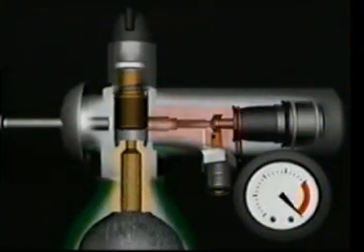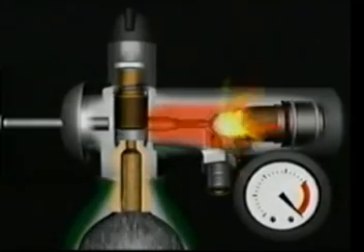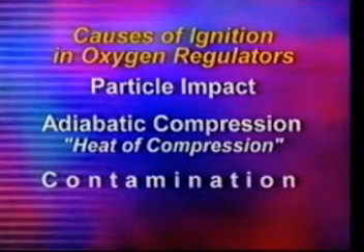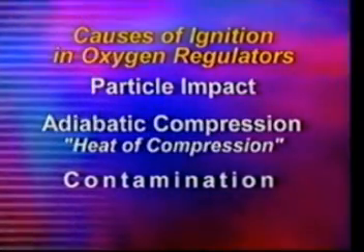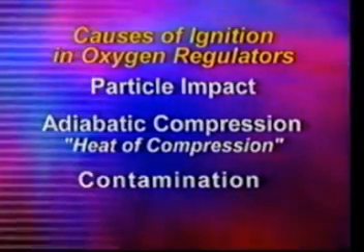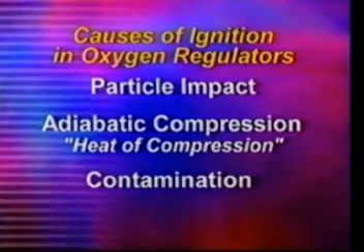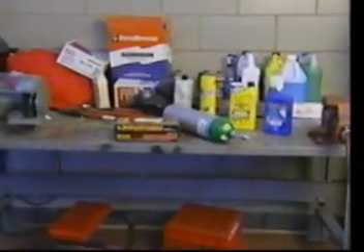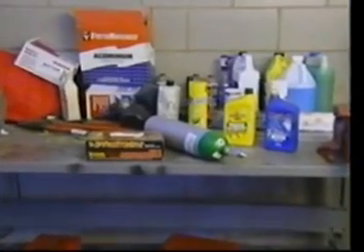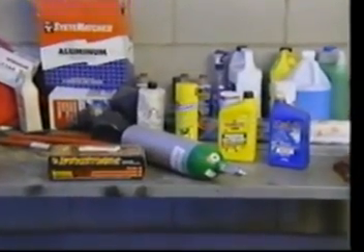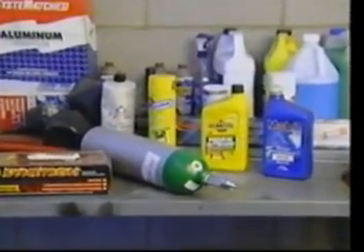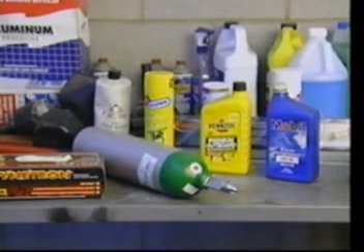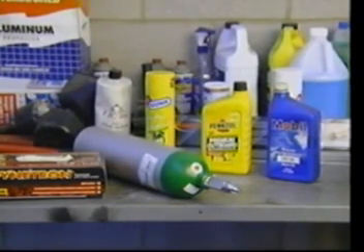That heat can also ignite contaminants inside the regulator, which brings me to my next point: contamination. This involves exposing parts of a regulator or a cylinder to a contaminant like grease or an oil-based lubricant — parts that come into contact with the high-pressure oxygen. Those contaminants are very easy to ignite, either by particle impact or adiabatic compression.